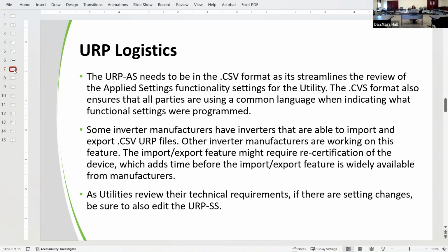settings were properly done. Prior to 2018, when IEEE 1547 was only the 2013 version, there were a lot fewer settings that the utility cared about. It was pretty much, okay, are you doing constant power factor? And then are you waiting your 5 minutes after an outage before it comes back on? Otherwise, we just basically told the inverters that any sort of system interruption, please trip off and stay off.